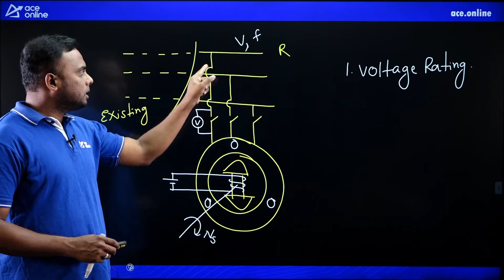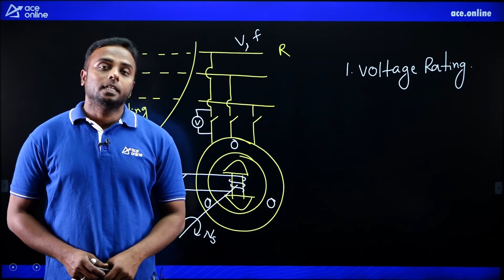Now which one do we have to adjust so that the voltmeter reading will become 0, such that both are said to be at the same voltage rating? In order to change the voltage of the alternator, generally we prefer to change the excitation of the alternator, maybe increase or maybe decrease. Whenever excitation changes, flux changes, and voltage will change. So excitation variation is easy for us. The voltage rating can be verified by a voltmeter across the two systems. If the voltmeter is not showing 0 reading, then adjust the excitation of the alternator until the voltmeter indicates 0. Like that we can easily adjust this.